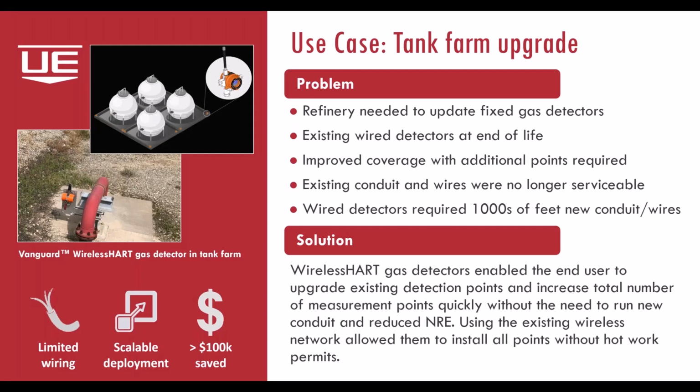And again, their scaling is up very quickly. They don't have to do the wiring, but they're plugging into an existing WirelessHART infrastructure that they had already in place for process control, not process monitoring. And they were very happy that they were able to plug in and look at the device. It was very familiar. If they had any questions, they could reach out to us. They could reach out to the gateway manufacturer, and both of us were able to support and work together to resolve any questions they might have had.